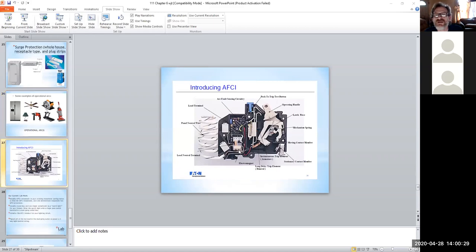Here's a cutaway of the AFCI. You can see in the front part it's very much like the old styles, with the typical circuit breaker spring and the little copper braid - electromagnetic functions run right through this. But over here, we've got a whole active circuit board, where this thing is literally an active device versus a passive device. On the right-hand side, that's passive - it's waiting to react. This one is reacting all the time. That's the difference between active and passive: waiting to react versus constantly there, looking to react.